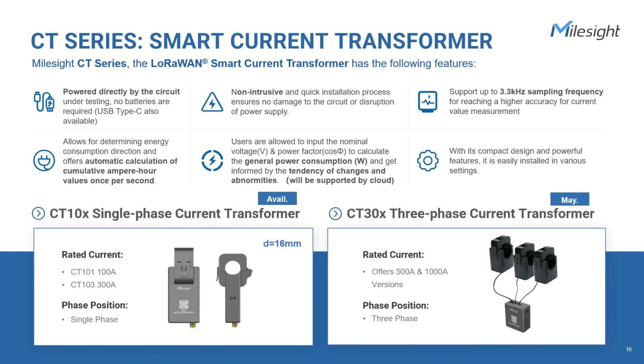The CT series consists of 2 types: CT10X and 30X. As the name suggests, the CT10X is designed for single-phase monitoring, while the 30X is suitable for 3-phase monitoring. Each variant has different detecting ranges: the 101 supports up to 100 amps, the 103 supports up to 300 amps, and the 30X offers options of 500 and 1000 amps. All three probes of the same device have identical measuring ranges.